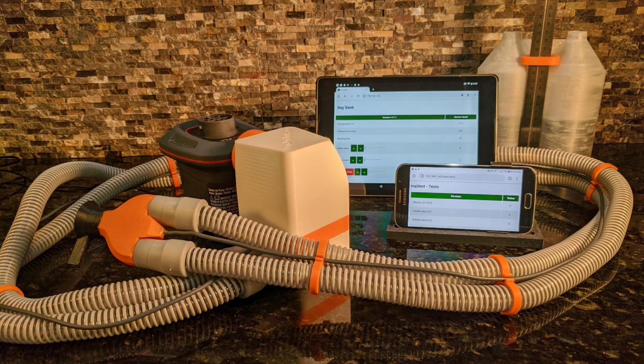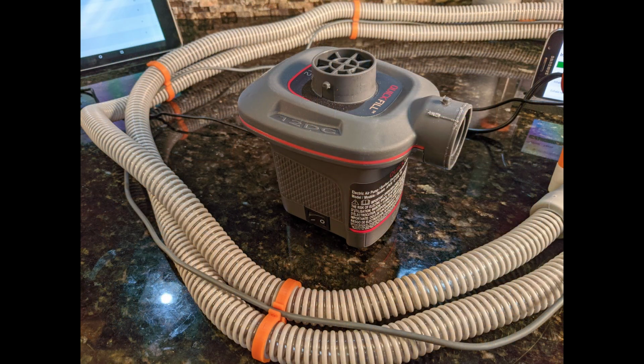Now, let's jump into the subcomponents that make up InqVent. This is InqVent prototype number 7. It is still in development and full functionality will be achieved in the coming weeks. Here is a breakdown of the major components. First up is the air supply. This is an off-the-shelf 12-volt air mattress pump. At peak output, it can supply pressure up to about 30 centimeters of water. As the common pressures needed for ventilation are around 10 centimeters of water, it has been derated to increase longevity and reduce noise. As you might imagine, these pumps are quite loud. It is expected that a lined sound deadening box could easily be made out of plywood or MDF.